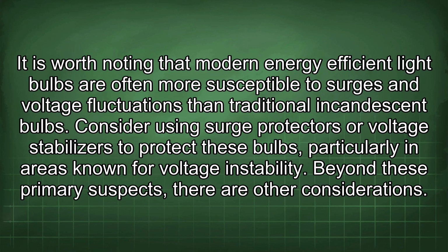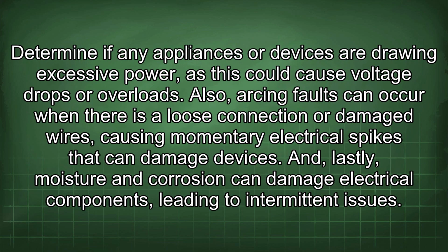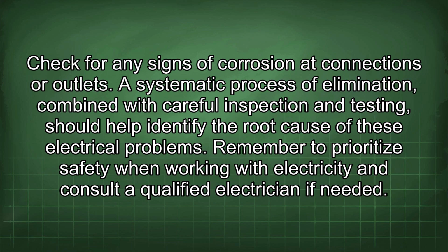Beyond these primary suspects, there are other considerations. Determine if any appliances or devices are drawing excessive power, as this could cause voltage drops or overloads. Also, arcing faults can occur when there is a loose connection or damaged wires, causing momentary electrical spikes that can damage devices. And, lastly, moisture and corrosion can damage electrical components, leading to intermittent issues. Check for any signs of corrosion at connections or outlets. A systematic process of elimination combined with careful inspection and testing should help identify the root cause of these electrical problems. Remember to prioritize safety when working with electricity and consult a qualified electrician if needed.